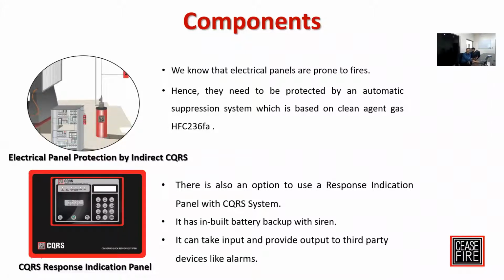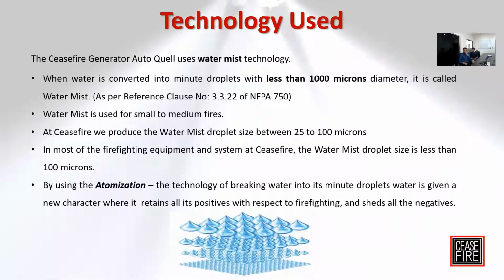Because water mist requires some area to develop as a mist. The electrical panels are so small that it does not allow the mist to develop. So therefore, for electrical panels we are not choosing a water mist system, we are choosing the gas-based system. But inside the generator, there is no problem. Let's talk about the water mist technology.